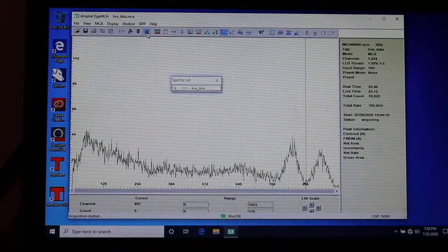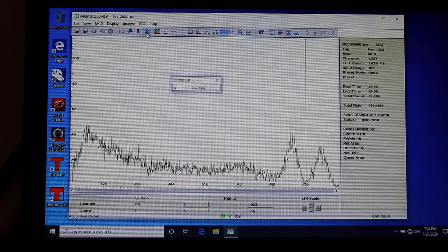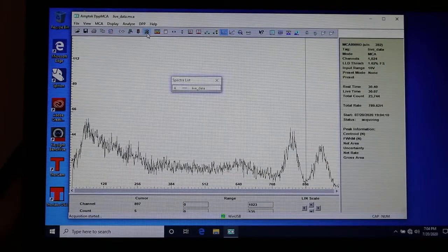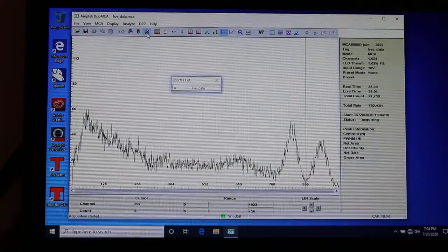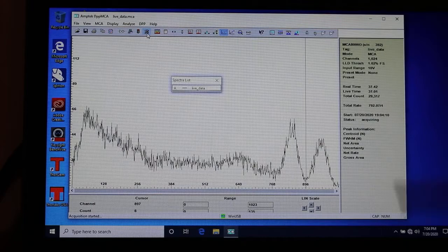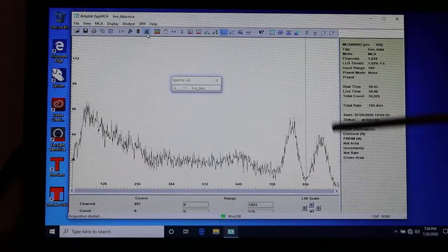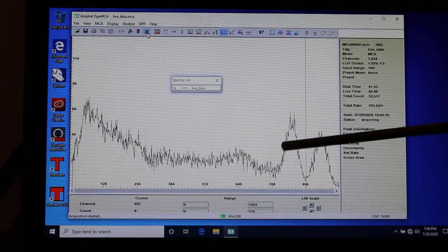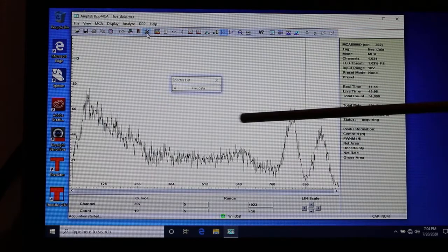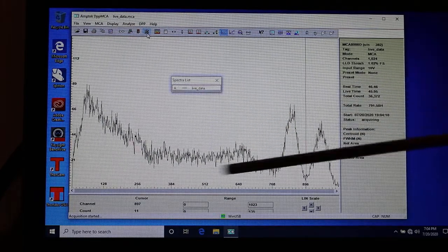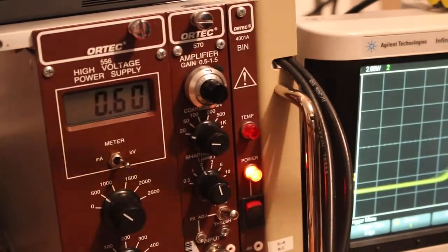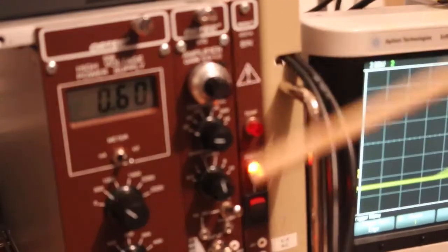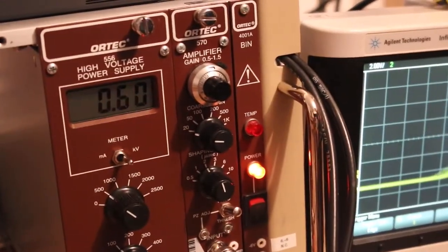And so what we can do now is absolutely promise ourselves not to touch the amplifier anymore. We have the gain set in an empirical way, just to park the highest energy gamma emitter we have over here in the highest bin numbers. Because everything else has a lower gamma ray energy, we expect their peaks to appear over here. If we're really going to be serious about this, we could even put a piece of blue painter's tape over the knobs. Just don't touch them anymore.